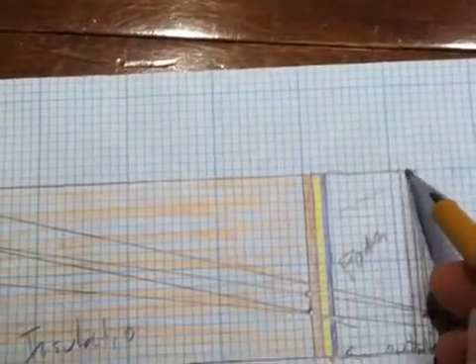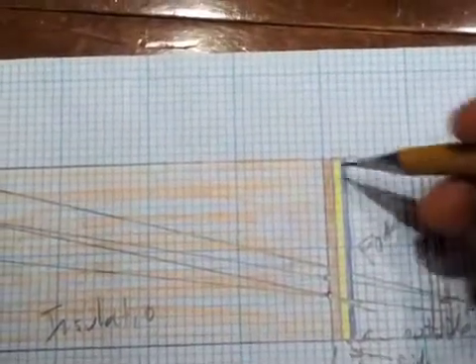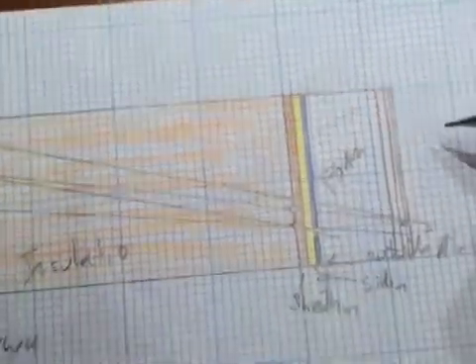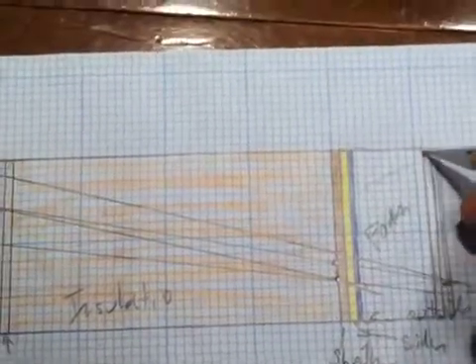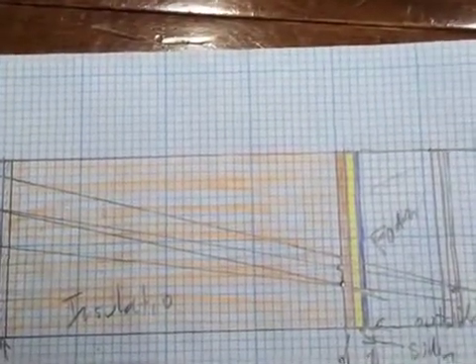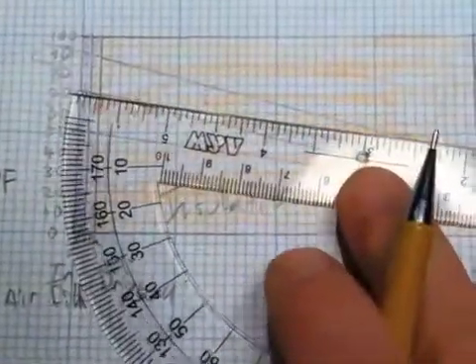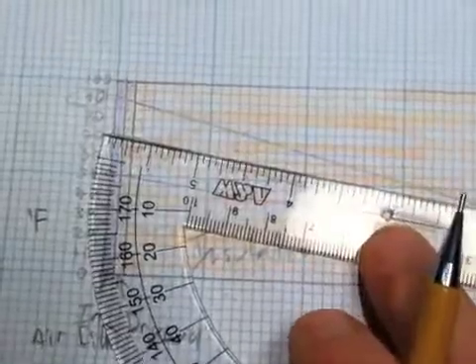So raising the temperature on the inside isn't everything we need to do. So then we know, to be safe, we ought to probably add more R value to the outside of that wall, outside of that first condensing surface. And so let's just pretend we did, and we add another R5. And now we're going to be back to our 70 degrees inside and our 20 degrees outside. And there we see that it crosses just below the 50 degrees mark.